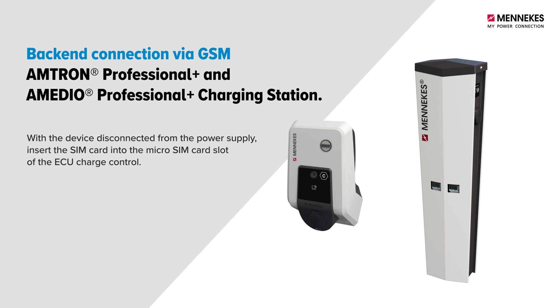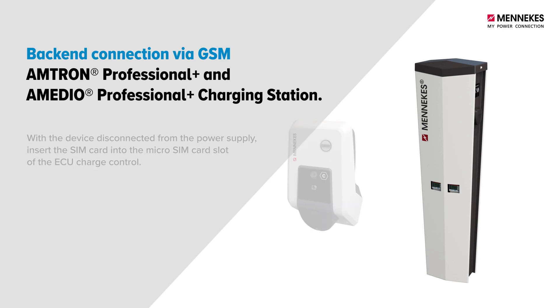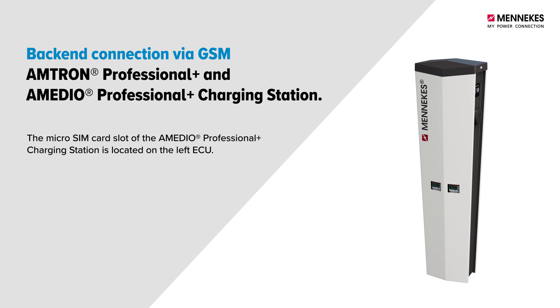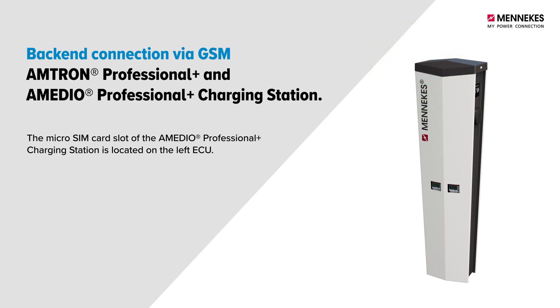With the device disconnected from the power supply, insert the SIM card into the micro SIM card slot of the ECU charge control. The micro SIM card slot of the AMEDIO Professional Plus charging station is located on the left ECU. Please refer to the operating and installation instructions.